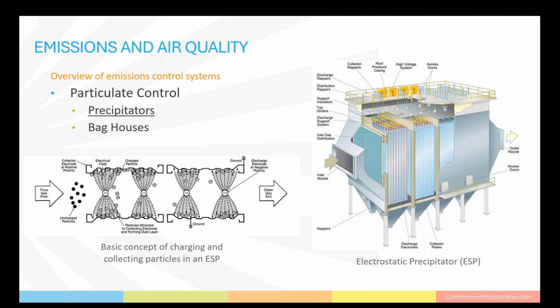Particulate control and boiler application is handled with precipitators and/or bag houses. They're typically used when very high efficiencies are required for removing fine particulate matter. ESPs can be installed downstream of the air preheater at temperatures of 270 F to 350 F. They are referred to as cold side ESPs, and they can also be installed upstream of the air preheater where the temperatures are in the range of 600 to 750 F and referred to as hot side ESP. They will require ash removal equipment in the form of collection, storage hoppers, and conveyors.